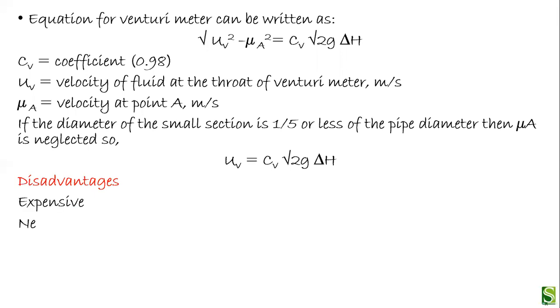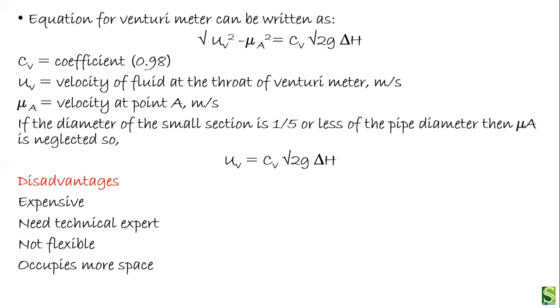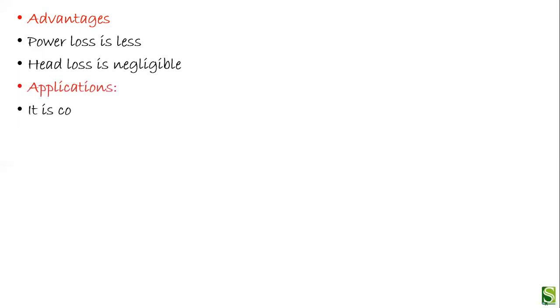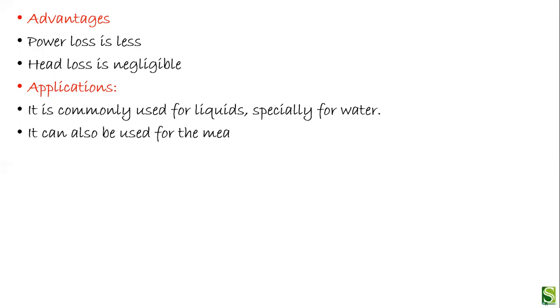The disadvantage of the venturi meter: it needs a technical expert, it is not a flexible method, and it occupies more space. However, it has advantages as well — power losses are very less, and head loss is negligible. Applications: it is very commonly used for liquids, especially water, and can also be used for measurement of gases.